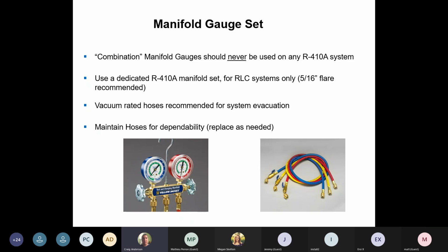Check out your gauges. Make sure the O-rings are good. Lube them up a little bit with some synthetic oil. Get them ready. These seals will dry out. It will cause your vacuum not to pull a vacuum if you're leaking out of your gauges and that. Make sure your hoses are good. They're not cracked and they're ready to go.